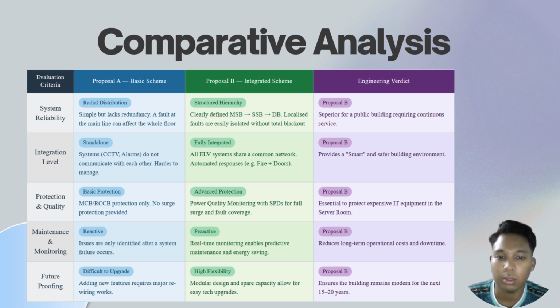And the next one is protection and power quality. Proposal A provides only basic MCB and RCCB protection with no surge coverage. But proposal B adds power quality monitoring and surge protection devices, which is essential for safeguarding sensitive IT equipment in the server room. After that, maintenance and monitoring. Proposal A is purely reactive. Problems are only discovered after a failure occurs. And proposal B has real-time monitoring that enables predictive maintenance. So it will reduce downtime and long-term operational costs.